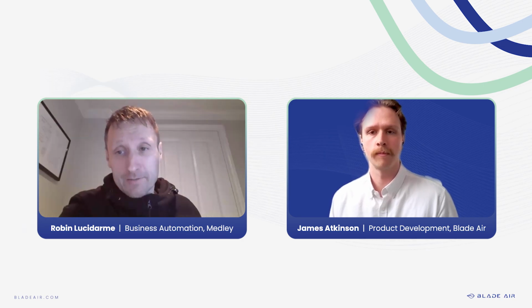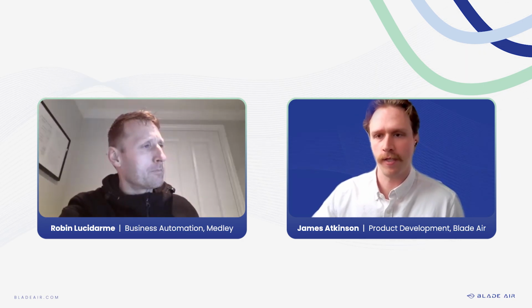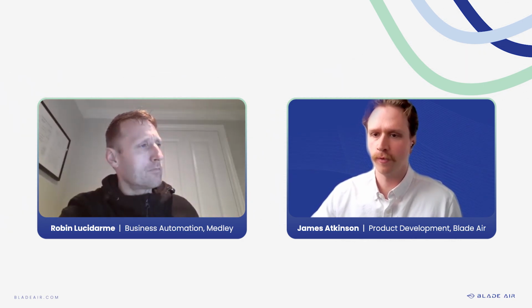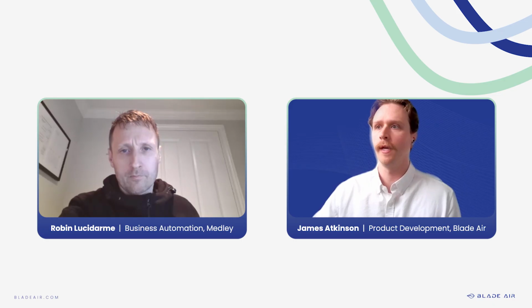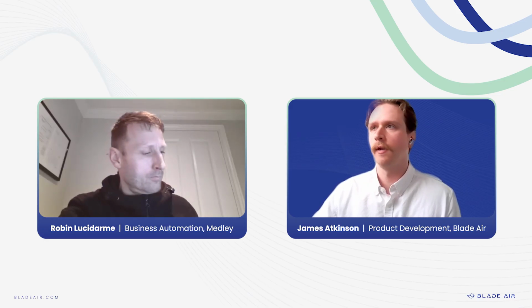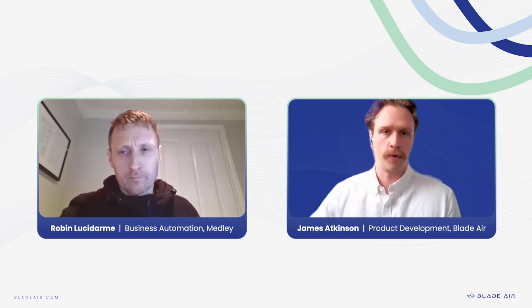So another question, let's say an RTU uses 2-inch pleated filters. Would this be a straight swap? Absolutely. So these are like for like. You give us the size of your current filters, we will return you a Pro filter that fits that exact spot. We have a 1-inch and a 2-inch model. So the one shown here is our 2-inch. And you will just drop them in. The only difference, you have to plug them in.